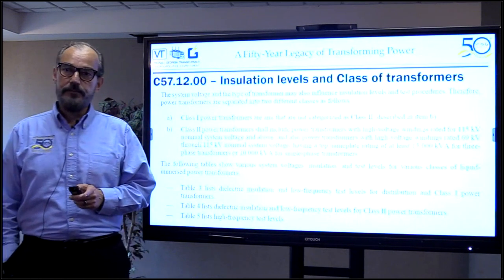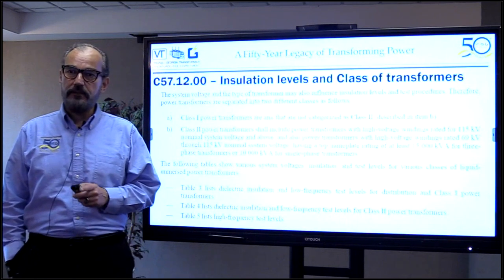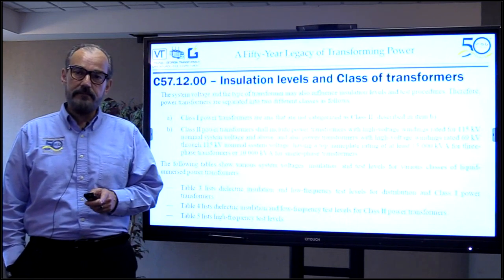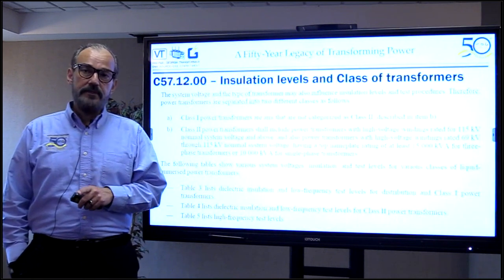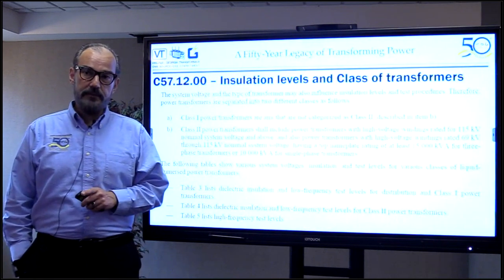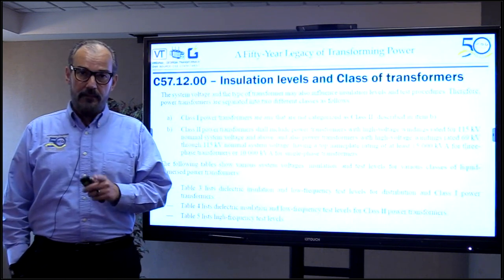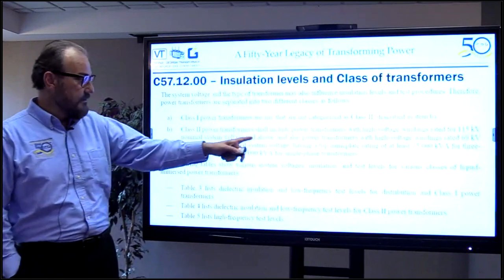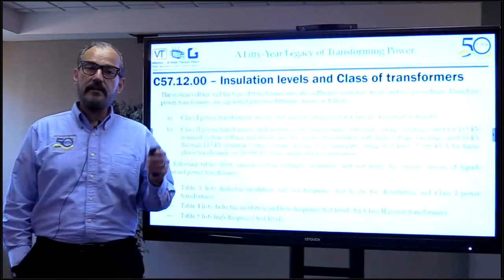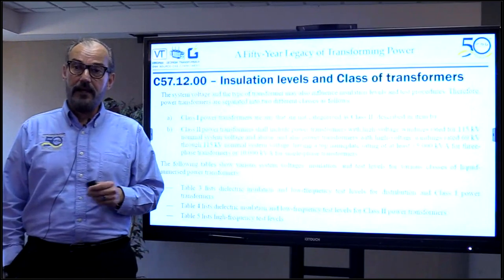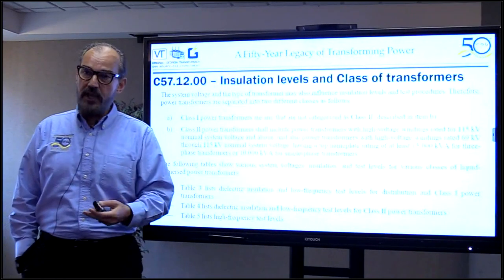Class two power transformers include those with high-voltage windings rated 115 kV nominal system voltage and above. This is the latest 2021 revision of C57.12.00. Previously, anything above 69 kV was class two — that was it — but the transformers committee changed that definition.